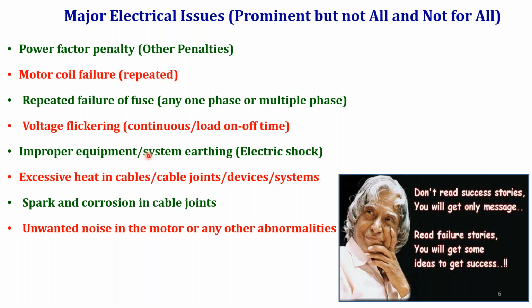Then excessive heat experienced in the cables, cable joints, devices, and even systems can be easily found with the help of a thermal imager or thermal gun, and automatically we are able to rectify it. Even heat in the system may also lead to energy loss. Then sometimes you can have spark and corrosion in the cable joint, unwanted noise in the motor, and any abnormalities in the systems.